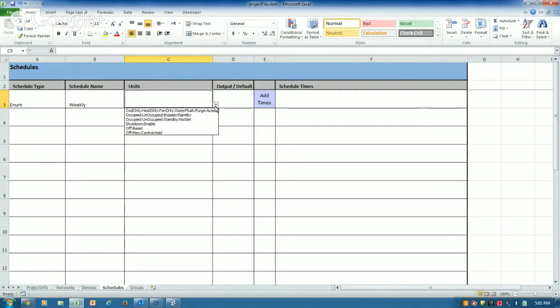Keep going, Matt. So here's what I'm doing now. My next tab is a schedule. I'll put in a default schedule, not necessarily the final one, but something to start with. I'll pick an enumerated schedule and call it my weekly schedule, choosing units like occupied, unoccupied, bypass, and standby as my standards.